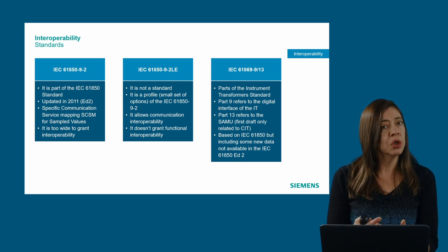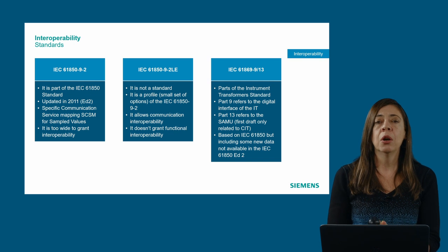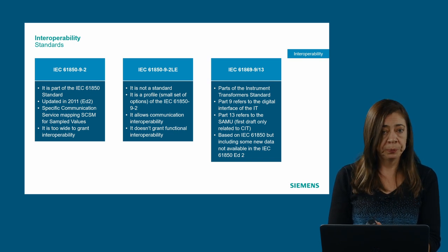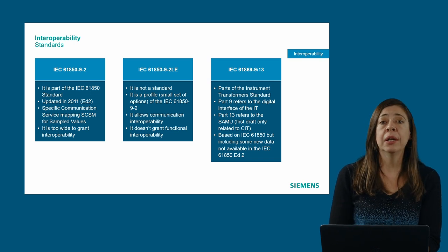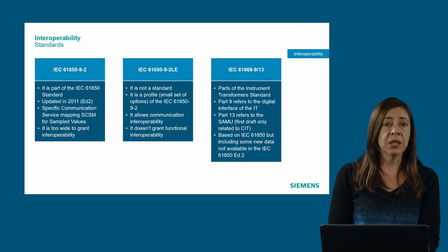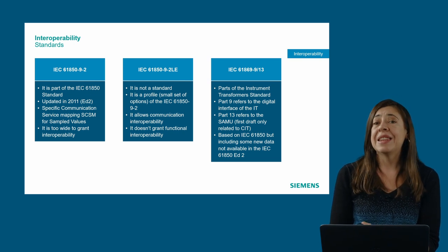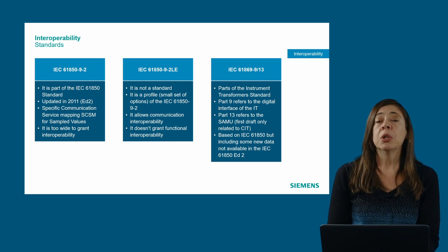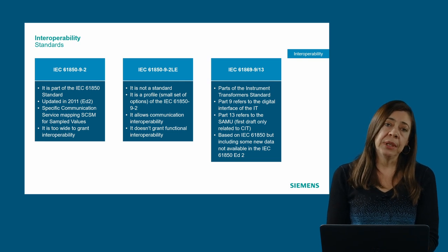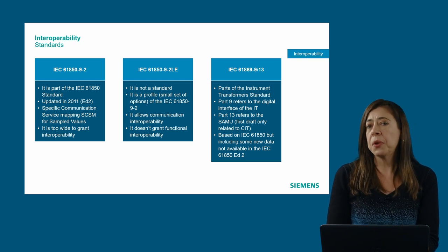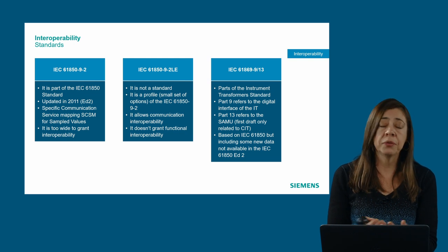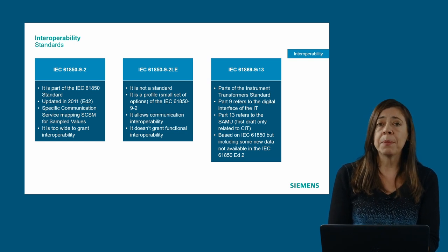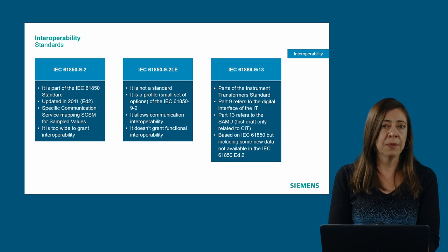The light edition is not a standard, it's a profile of the chapter 9-2. And it actually allows interoperability in communication, but it doesn't help when it comes to interoperability in terms of functionality. So later on, in 2016, the standard of the instrument transformers defined a couple of new settings and parameters which are required to grant this functional interoperability.